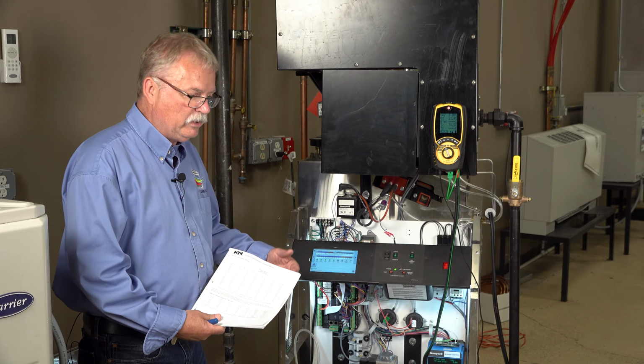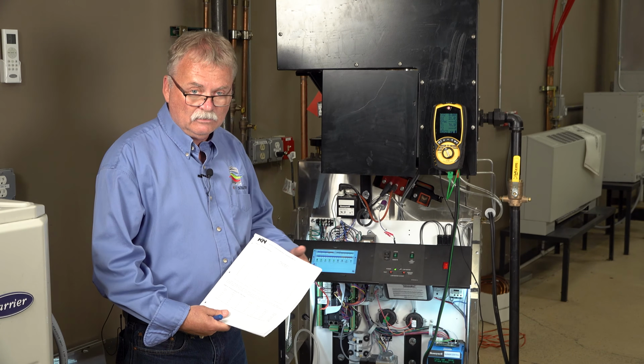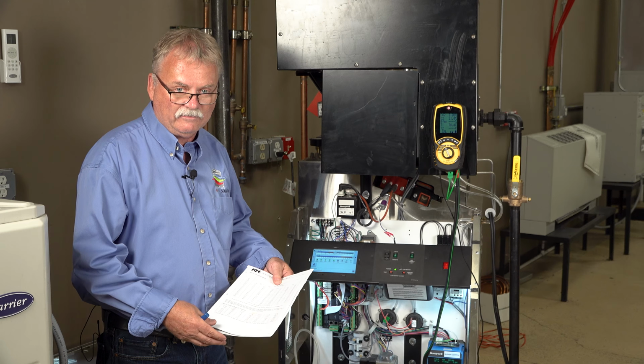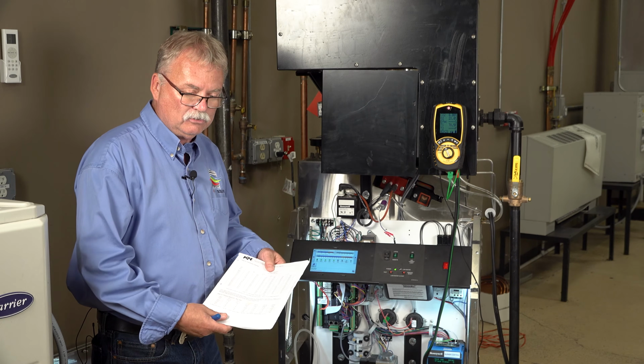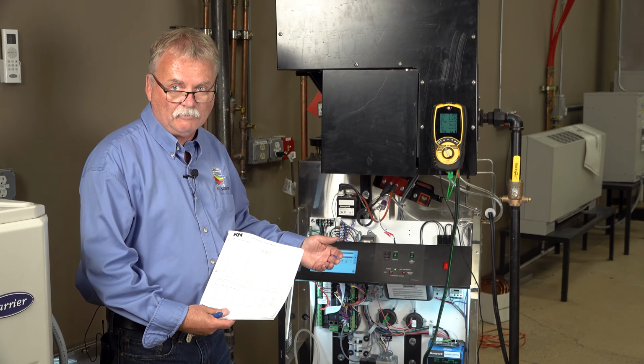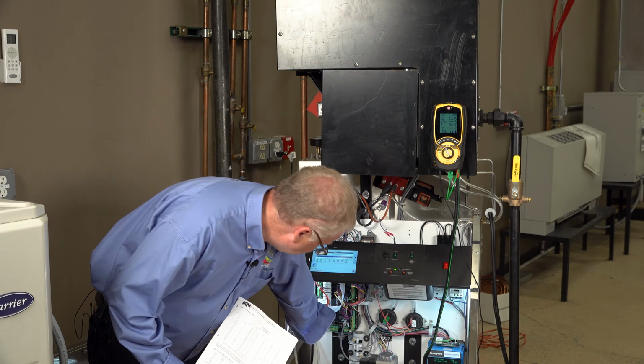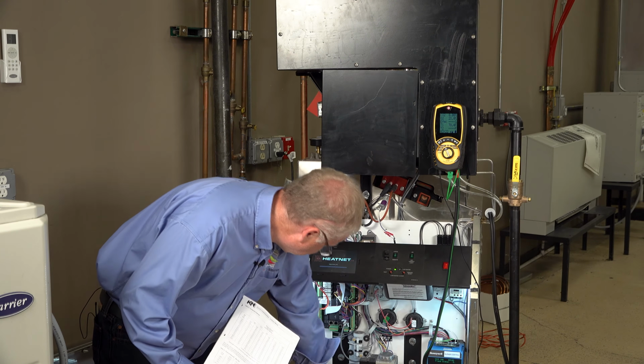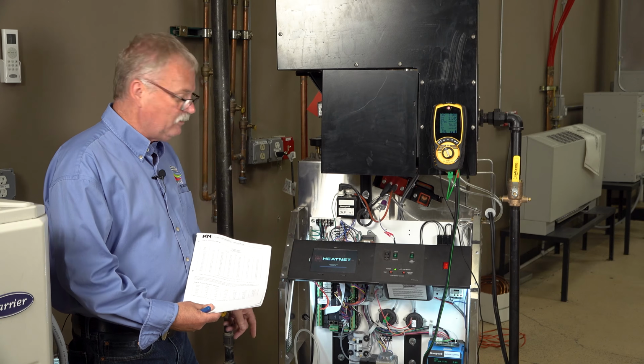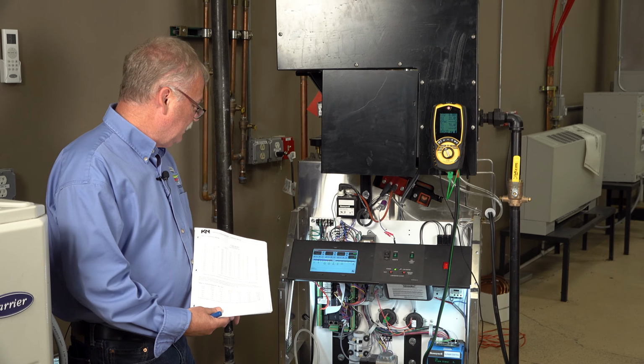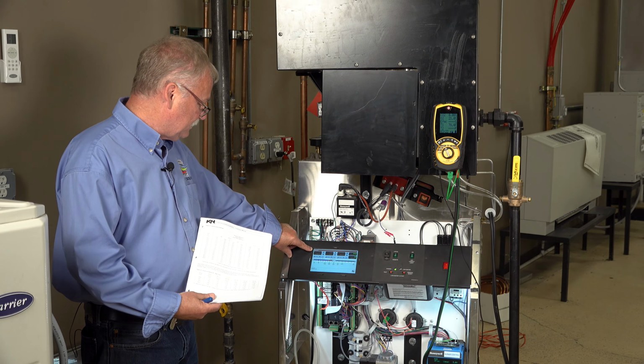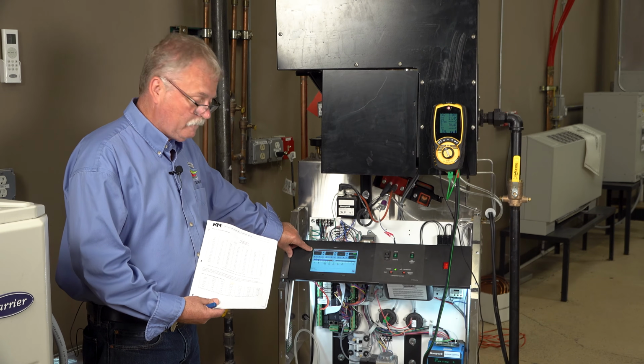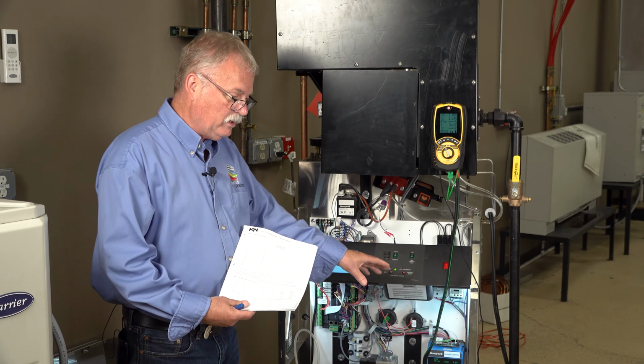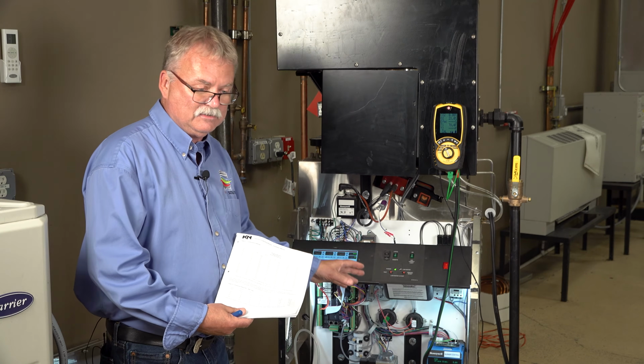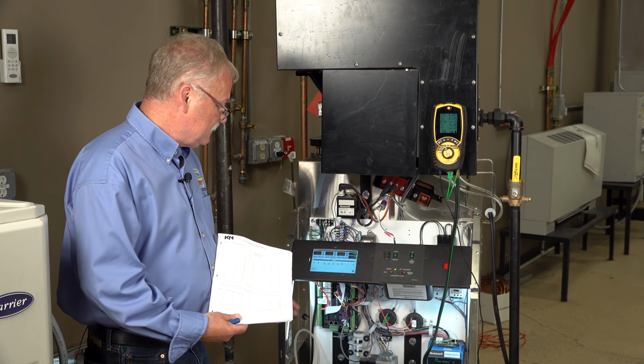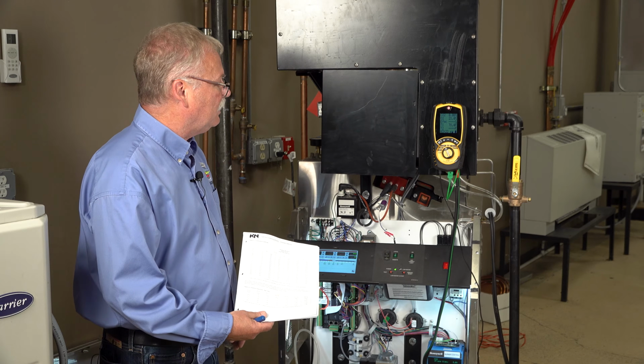I'm going to put it into what we call a calibration mode, which means I take over the control of the fan. By taking over the control of the fan, I can control the combustion up and down. This boiler happens to have 2 little switches here. As you see, the screen changed now since I'm taking over. And now I'm in, just like it says here, calibration mode. You're going to hear some noises and that kind of stuff. That's because this boiler isn't tuned in right now. All right, so we're going to let it settle out.